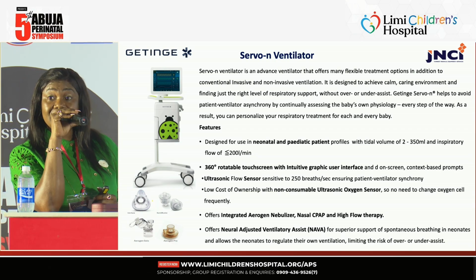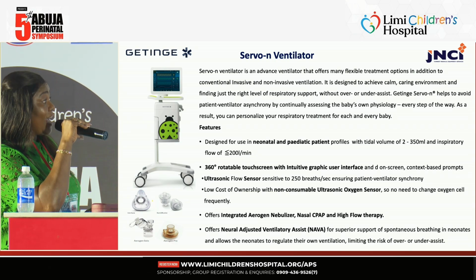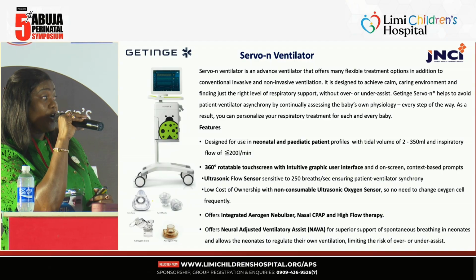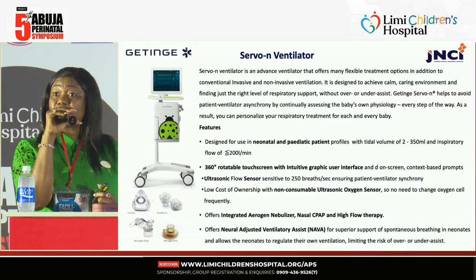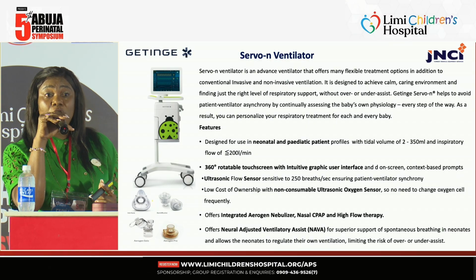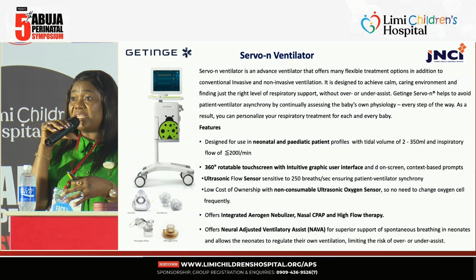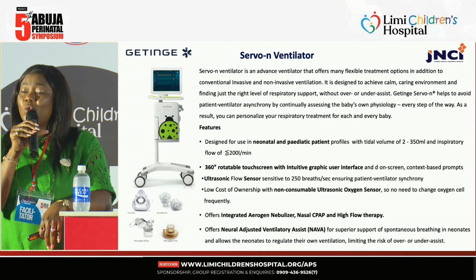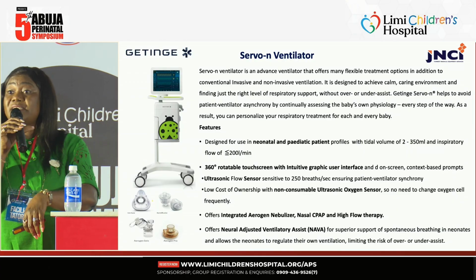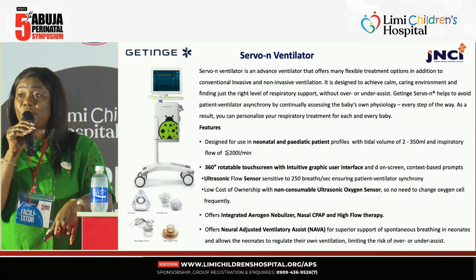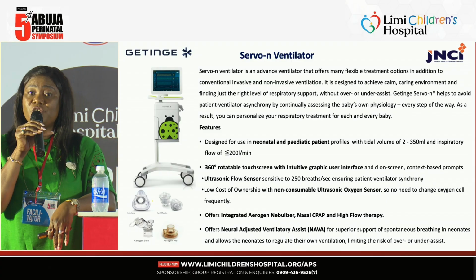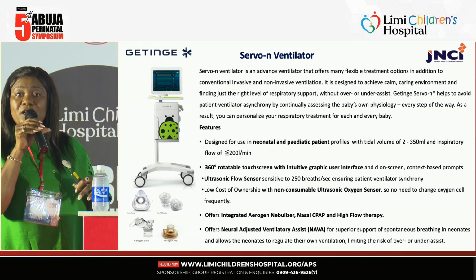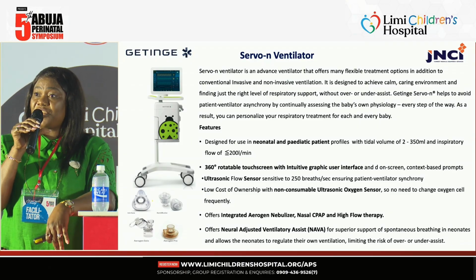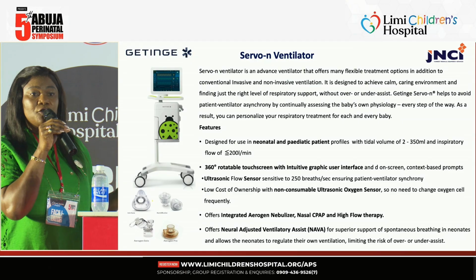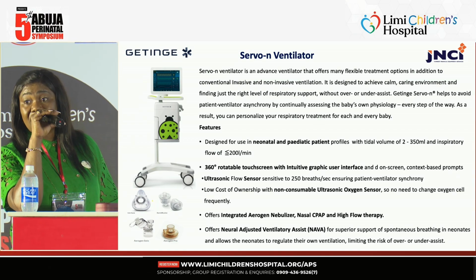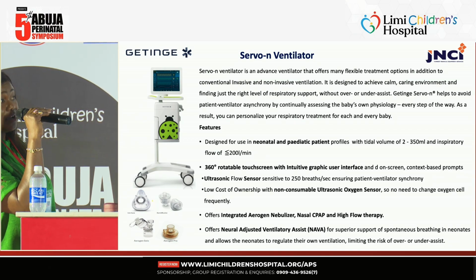It is aesthetic to look at, very user-friendly, and also very durable. It ensures that there's a low cost of ownership because it functions on ultrasonic sensors. So the regular ventilators that we have in the market function on what we call oxygen cells and oxygen sensors. However, this ventilator focuses on ultrasonic sensors. This ensures that the cost of ownership is minimized because an oxygen cell is expected to be changed every year. However, an ultrasonic sensor will last almost as long as your ventilator will last, which is several years.